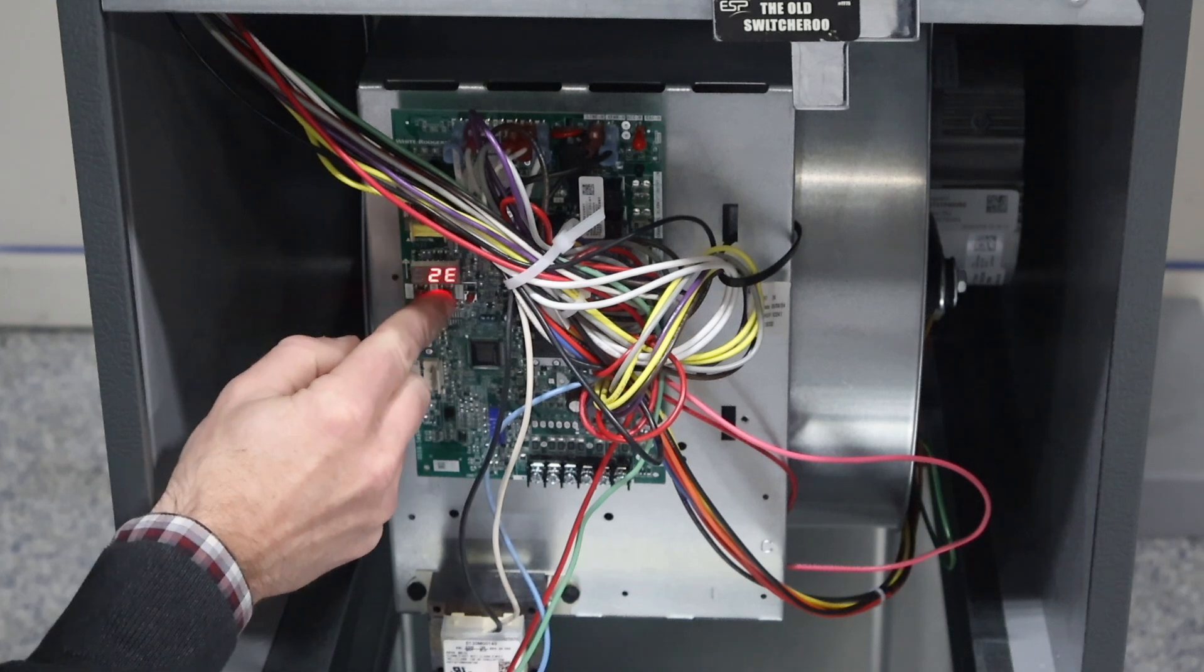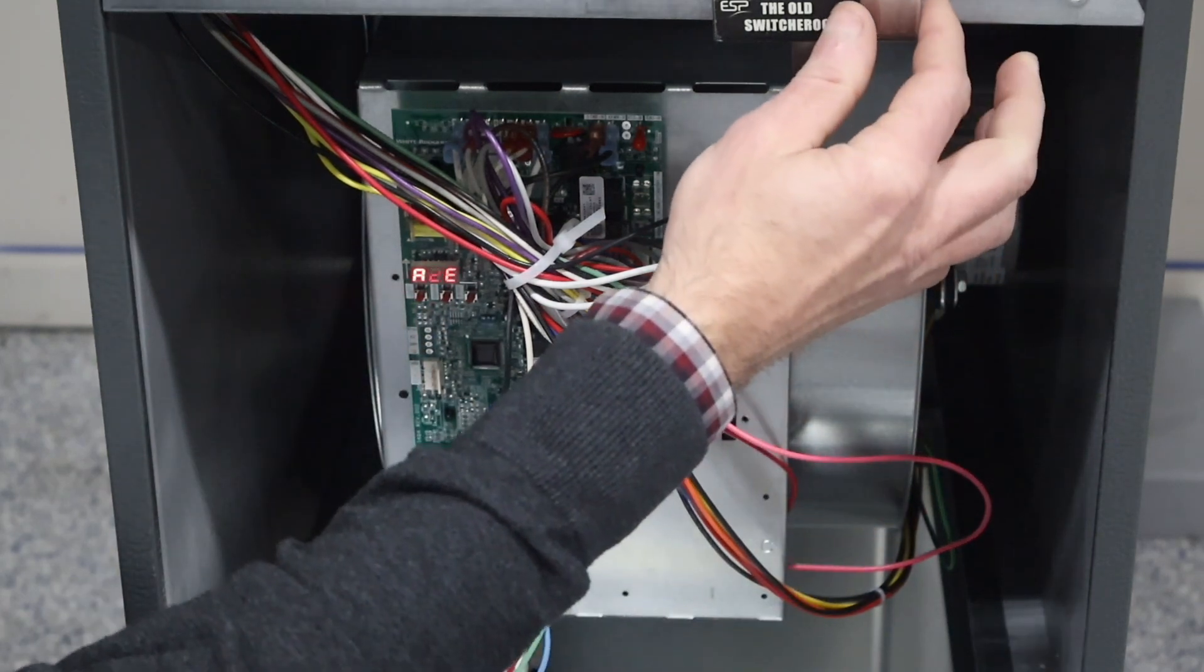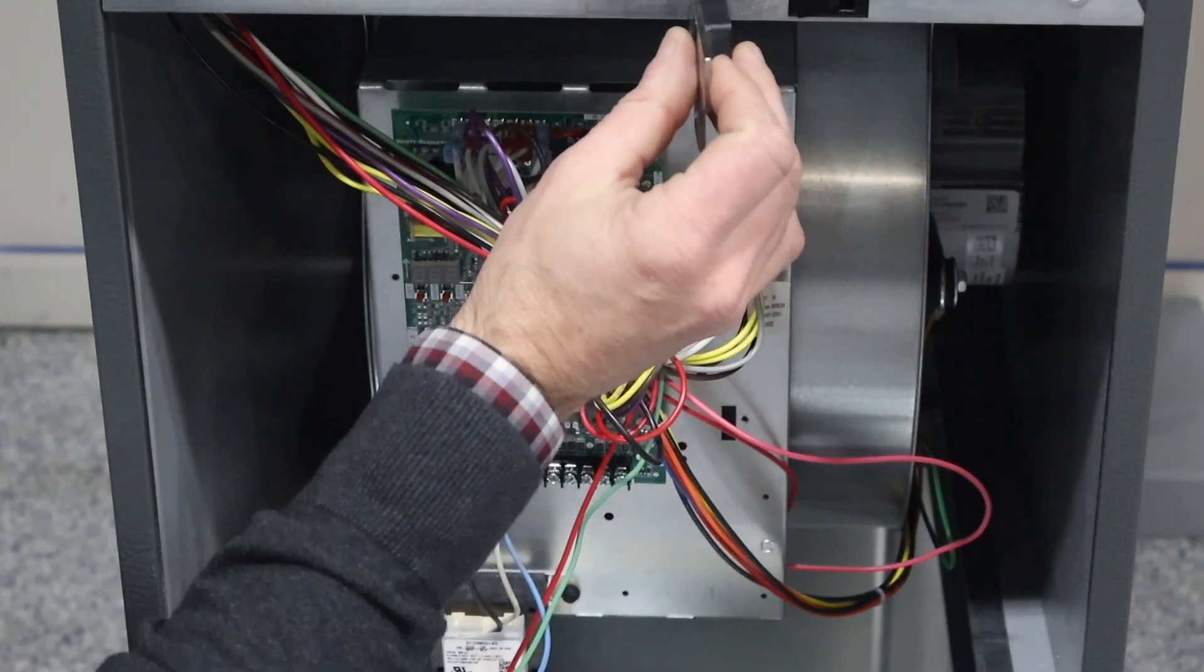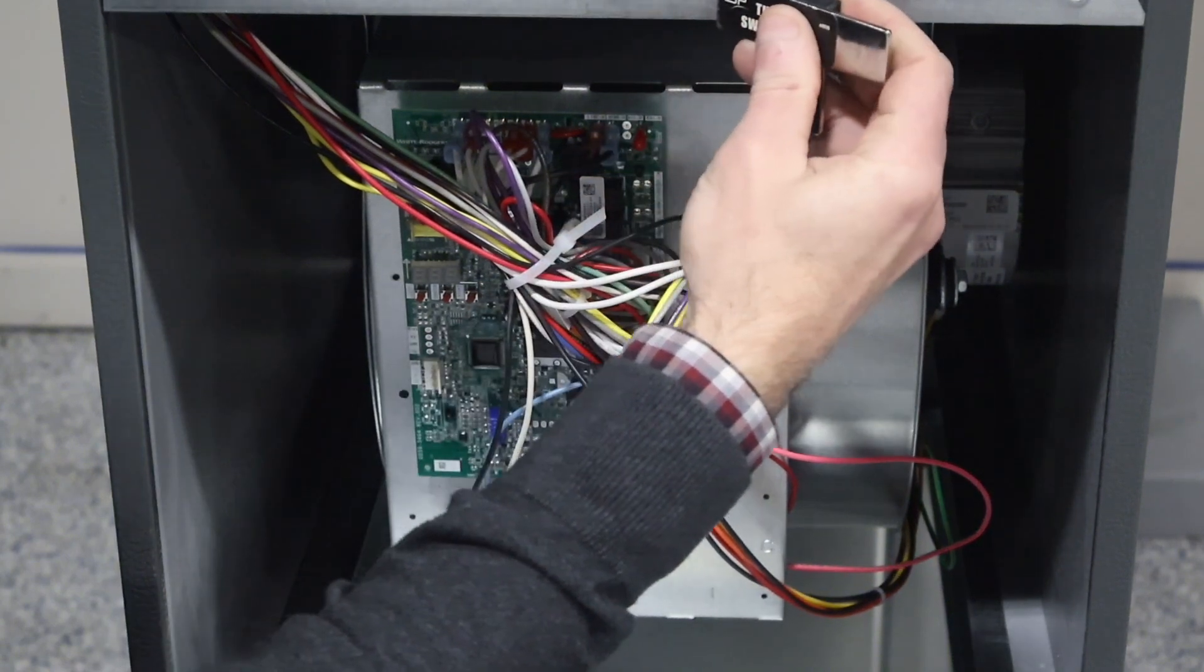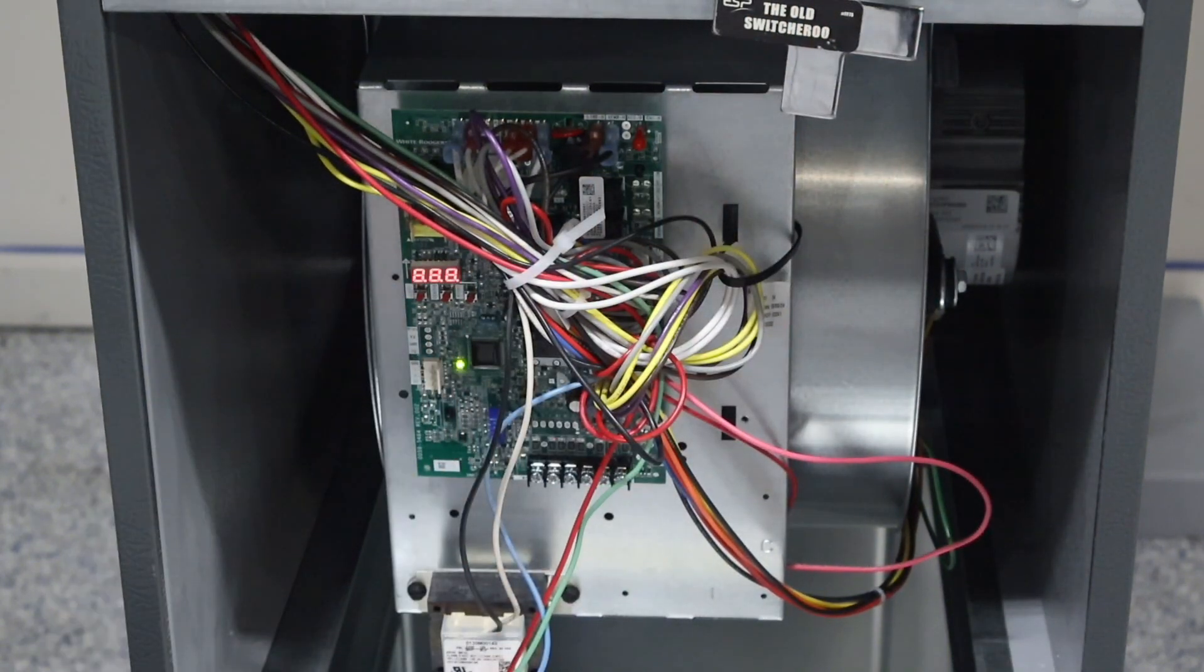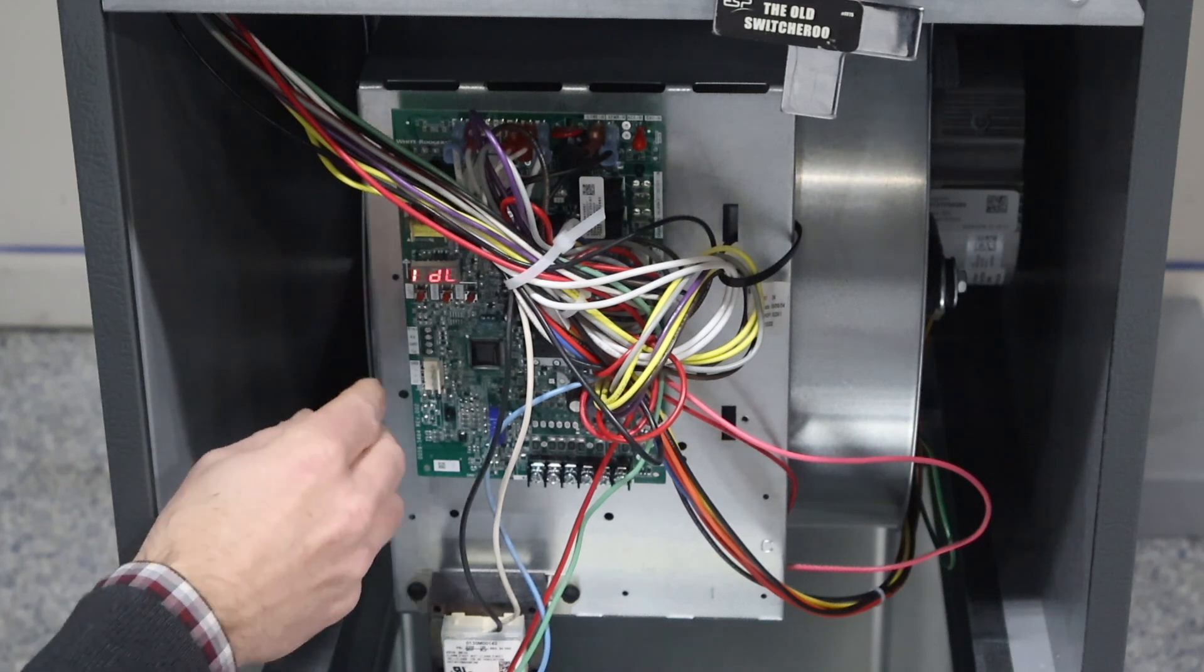We'll say A2E again, de-energize the system, then when we re-energize the system, it should be out of leak mitigation mode so it should no longer look for that A2L refrigerant sensor.